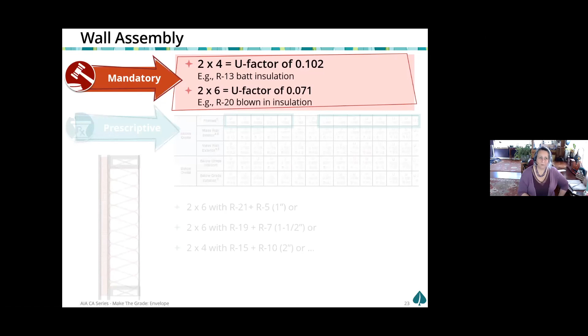With rebuild efforts happening in California, metal is being used more often because it's more resilient. But we have to think about what happens to energy performance when we use more metal, and consider encapsulating that metal framing with a product that has a rated R value to achieve these very low U factors. Our prescriptive U factor requirement for most climate zones is 0.048—that's a lot lower than 0.102, isn't it?